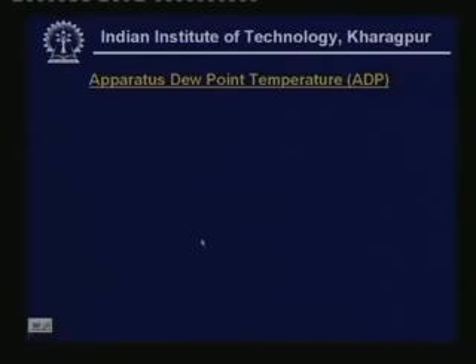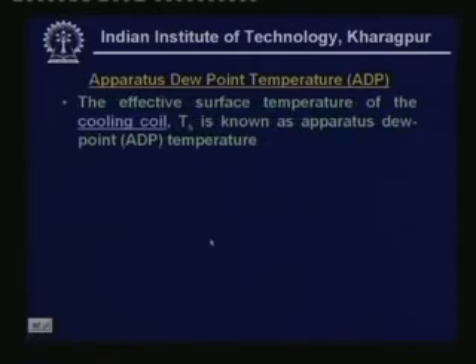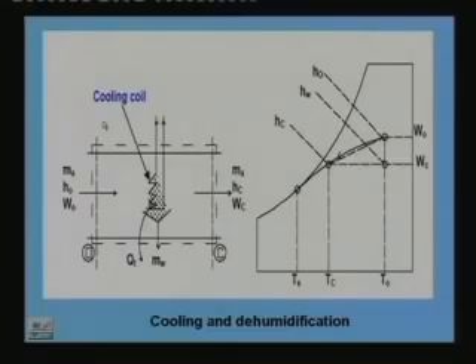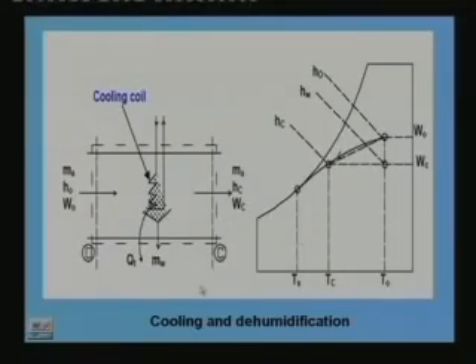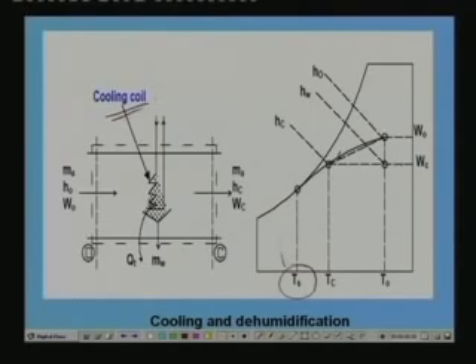Let us discuss another important concept called apparatus dew point temperature, or ADP. The effective surface temperature of the cooling coil, Ts, is known as the apparatus dew point temperature. In fact, the actual temperature of the cooling coil will be varying because of the boundary layer development and because of the temperature gradients in the fins, etc. But we can conceptualize an effective surface temperature for the coil, because the surface temperature does not remain constant on the coil. We can define an effective surface temperature, that means you will have a single value. You can see on the psychrometric chart here that Ts is the effective surface temperature of this cooling coil, and this Ts is known as your ADP, that is, apparatus dew point temperature. As I have already mentioned, if you know this temperature and the inlet condition, you can draw the straight line and the process path.